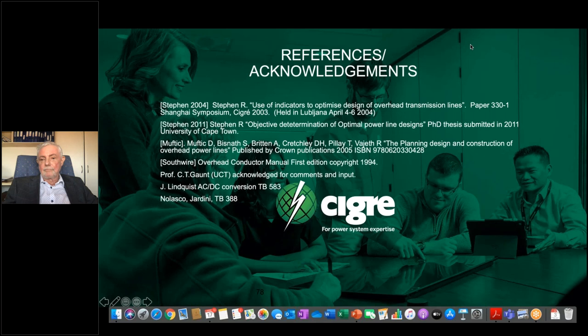There's a question here from Pierre Sattar. Do you think the uptake of the use of ACCC conductors and higher performance conductors will be considered by Eskom as a standard in the near future, considering that they typically have standardized on ACSR? You might probably need to ask Eskom that at this point. My opinion is, I can talk more or less generally, but the ACCC, remember, is a special conductor. It's a registered trademark, ACCC, carbon core conductor. It's a single core. I'd rather look at, if you take the question to say, are we looking at polymer core, in other words, stranded polymer cores or FRP type core conductors?